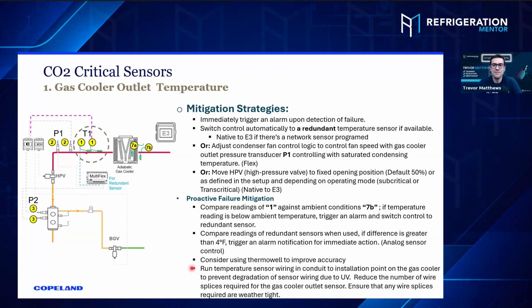And the other thing that the end users and engineers were talking about, that you're going to see over and over, is to run the temperature sensor wiring and conduit to installation point on the gas cooler to prevent degradation of sensor wiring due to UV. Maybe we don't get as much of that in Canada, but I can tell you, go in the south, man, and that sun's beating down over and over, day after day, hour after hour. That's a recommendation that is a good one. That'll come up over and over as we go through this.